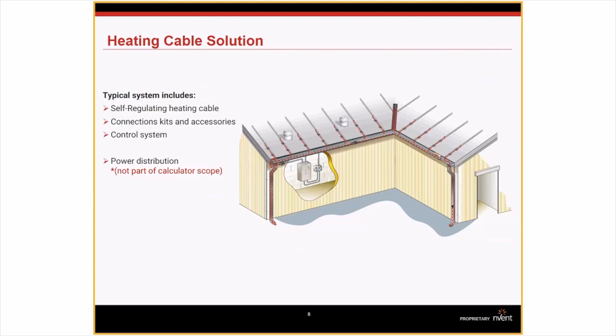Our roof and gutter calculator can design both a cable-only solution and a RIM system. For a cable-only solution, it calculates the amount of heating cable needed and suggests the necessary components and termination kits to complete the system. The calculator also provides the number and size of breakers required, though these must be provided separately and will not be included on the bill of material.